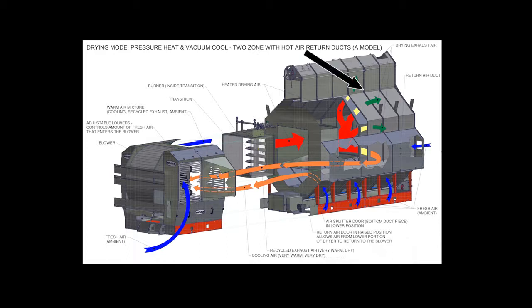Using pre-warmed air from the cooling section improves the dryer's energy efficiency. Additionally, the dryer's hot air return ducts can be used to draw warm exhaust air from the lower portion of the heat section and recycle it back through the fan, where the air will be mixed with fresh outside air from the louvers and the warm vacuum cool air drawn from the cooling section. Recycling warm air from the heat section further improves the dryer's fuel efficiency.